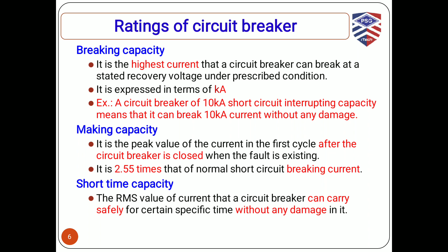Next, what is short time capacity? It is the RMS value of the current that any circuit breaker can carry safely for a certain specific time without any damage to the circuit or any of the components. That is what is called short time capacity. The next rating of the circuit breaker is the rupturing capacity. It is the maximum power the circuit breaker can interrupt under any fault. It is a product of the rated breaking current and the rated voltage, in kiloamps and kilovolts respectively.